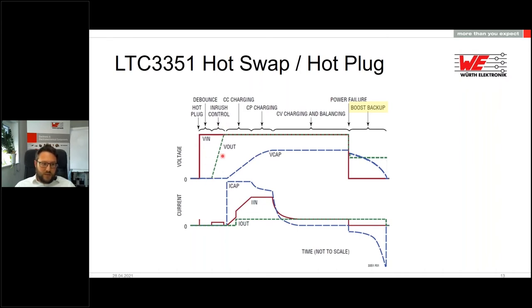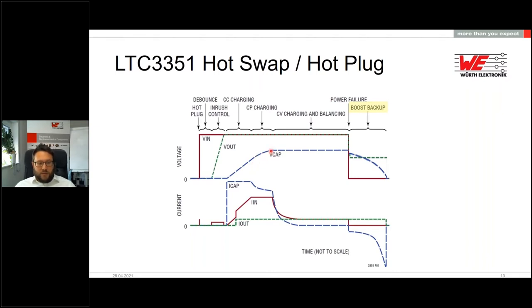Once the output capacitance is charged and the output voltage is stable, the IC starts to charge the supercapacitor bank. The first charging phase is constant current. When a threshold is reached, it switches to constant power, then to constant voltage charging with balancing. The IC keeps the supercapacitor bank charged and balanced, waiting until a power failure occurs — at which point the output voltage drops to 12 volts and the application is supplied from the supercapacitors.